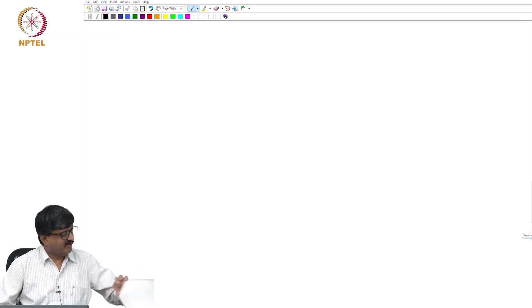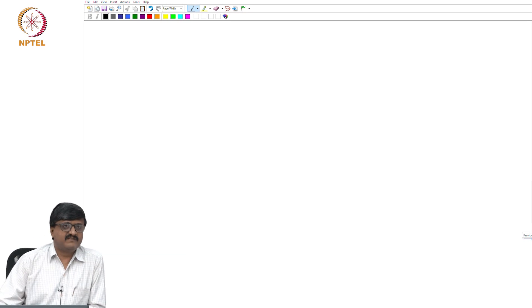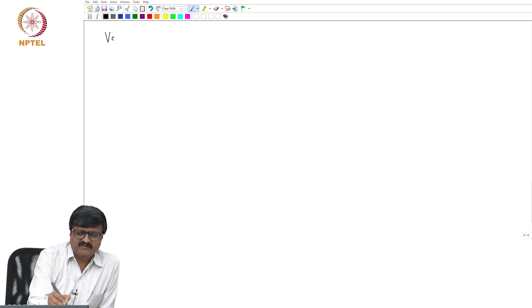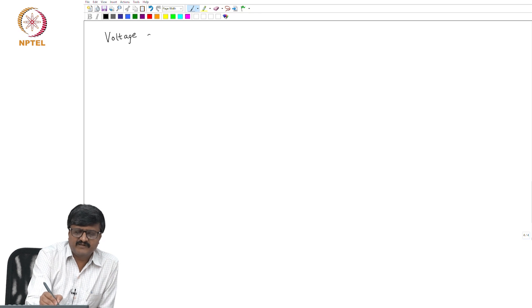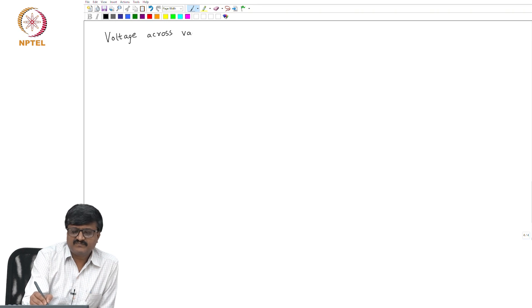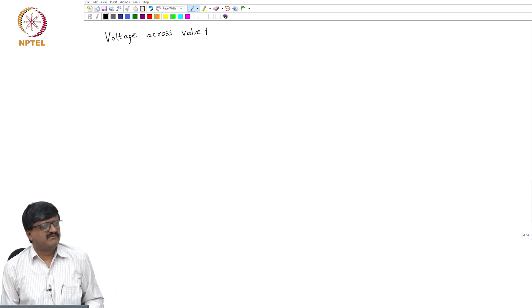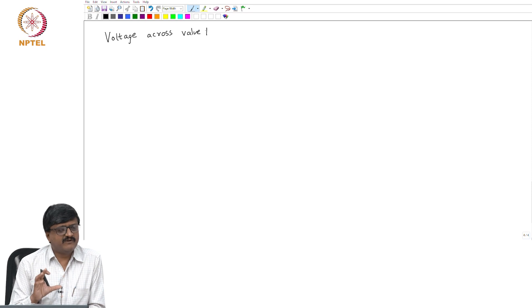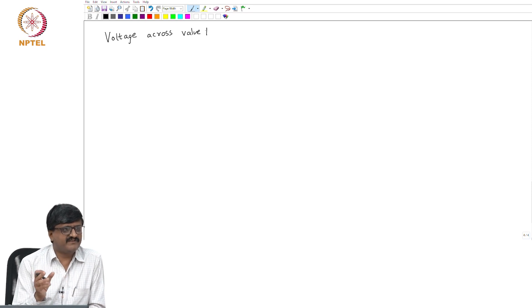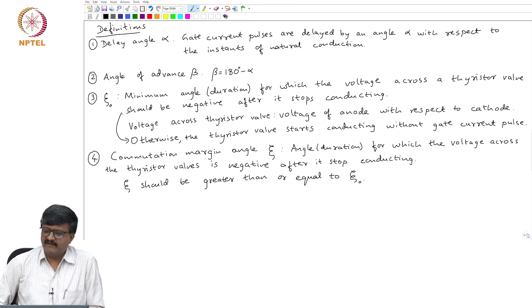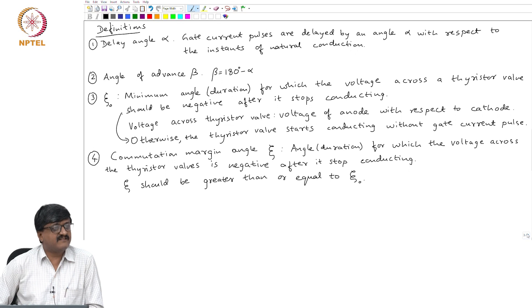Let us recall from the table that we formed a few classes ago — we got the expression for voltage across the valve. The last column gives voltage across one of the valves, valve 1. We consider only one of the valves because all the valve voltages will be identical except for a phase shift. Even going back to the definition of commutation margin angle, we say that is the angle for which the voltage across the thyristor valves is negative.